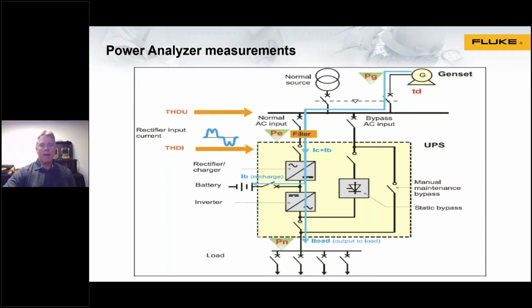And then after the installation, commissioning on an ongoing basis, and actually before you're done commissioning, you would do what's called a combined test. That's where you would actually not use load banks, but connect your critical loads. So these are the tests we're going to be looking at. There's a number of different tests. All would involve use of a power analyzer.